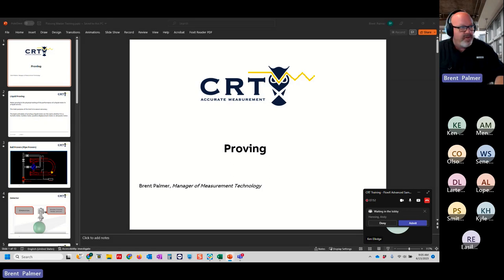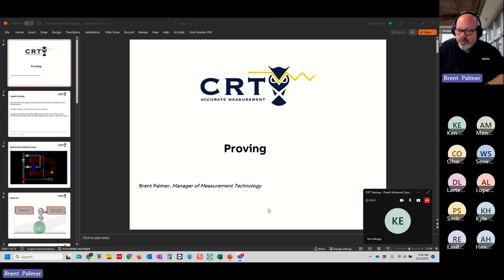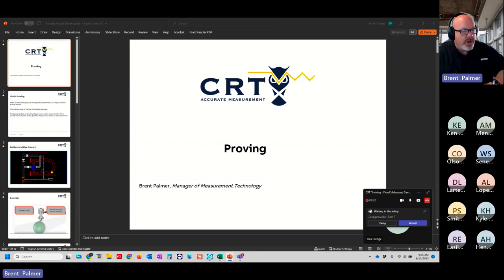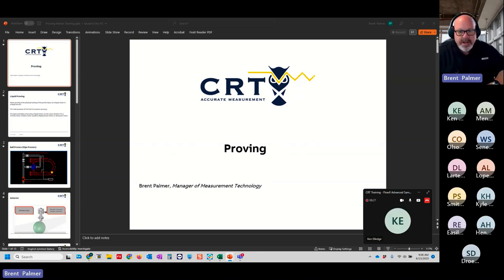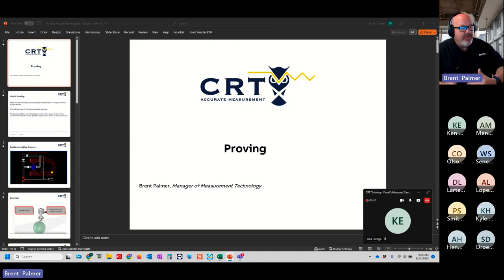We're going over proving. With liquid proving, what we're doing is physically testing the performance of the meter in liquid service. We're trying to assure the accuracy of the meter. The basic principles of liquid proving are the same whether it's a Coriolis meter, turbine meter, positive displacement meter, or ultrasonic meter — we're counting pulses, and those pulses equal either a volume or a mass. We then compare that against the volume or mass of the prover to determine the accuracy of the meter.